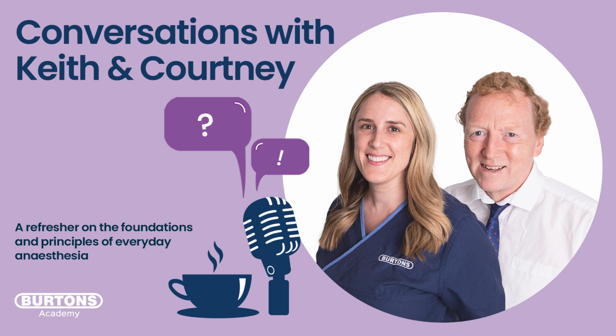But when we want to zero our IBP to atmosphere, so that what we start getting is just this nice fresh baseline from our patient, we end up shutting off 9 o'clock. Think of a 3-way tap, we turn it so that we open up between 12 o'clock and 3 o'clock. So where our saline bag is, our transducer, and then open to the atmosphere. That's all we're doing. We're just going from 3 o'clock and 9 o'clock being open to shutting off 9 o'clock and opening up 3 o'clock and 12 o'clock to zero our IBP to atmospheric pressure.